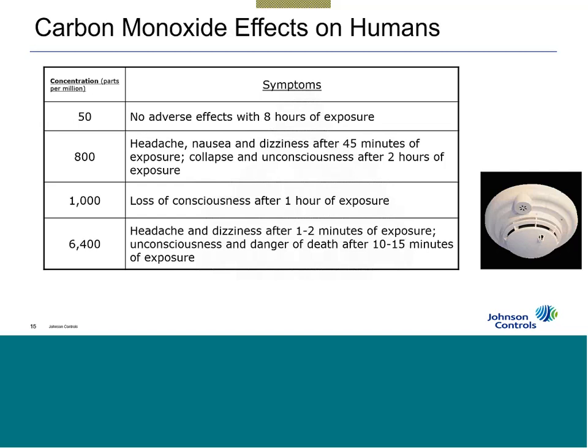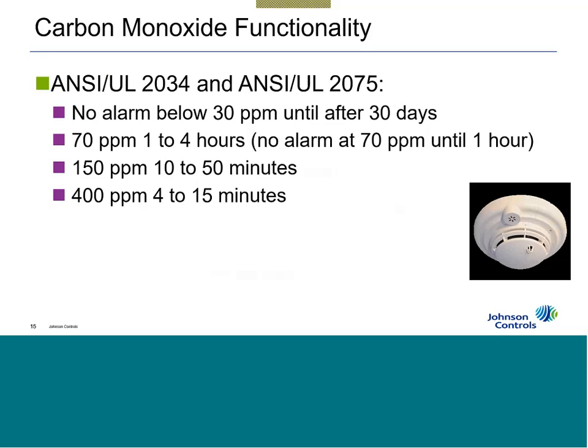So carbon monoxide detectors don't function like a smoke detector does. I don't need a certain amount of smoke and then boom, my detector goes into alarm. Heat detector, get to a certain temperature, boom, go into alarm. CO works differently. UL had to get involved because early on, CO devices actually did operate that way: they saw a little bit of CO and they went into alarm. And we had false alarm issues with carbon monoxide. Companies were under the gun, with a massive amount of nuisance alarm issues. The Consumer Product Safety Commission got involved. So UL came out and said, okay, let's develop a criteria for carbon monoxide devices to function. I have both listed here, UL 2034 and 2075. Whether you're a single station carbon monoxide device, standalone, or a system device, the functional requirements of how they operate are identical.